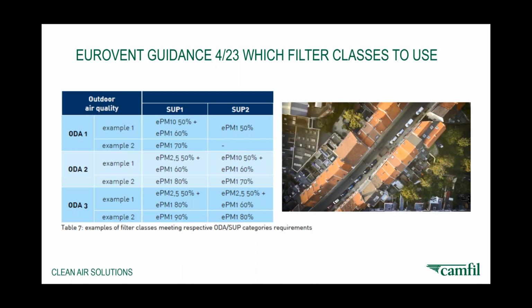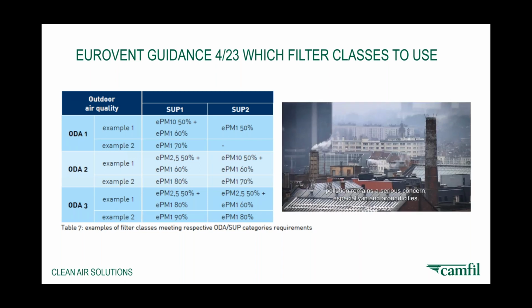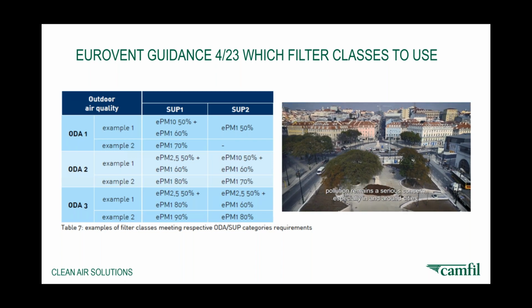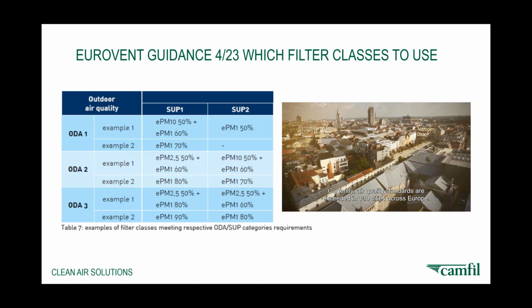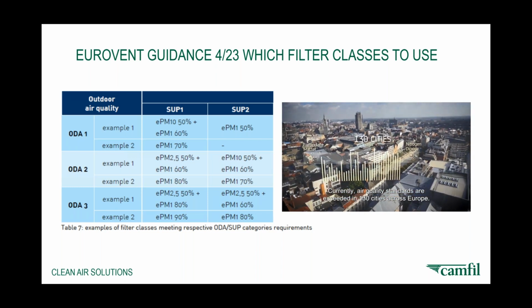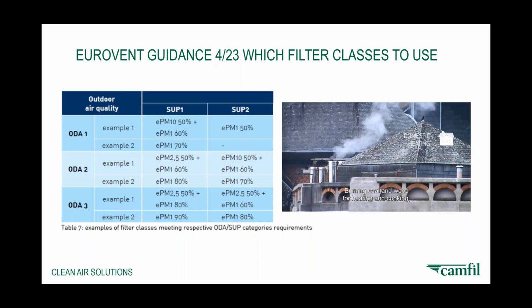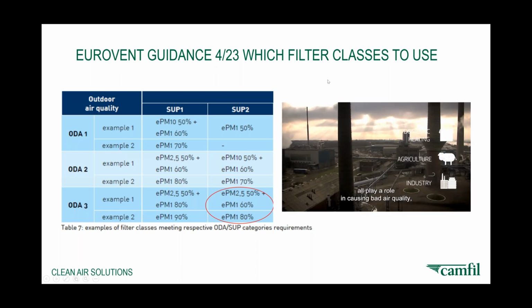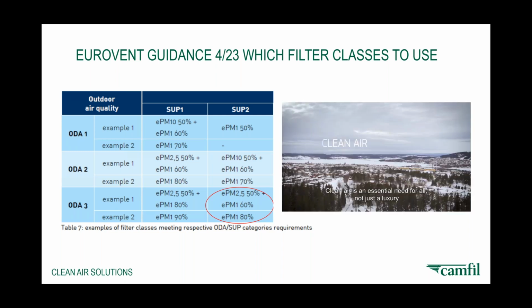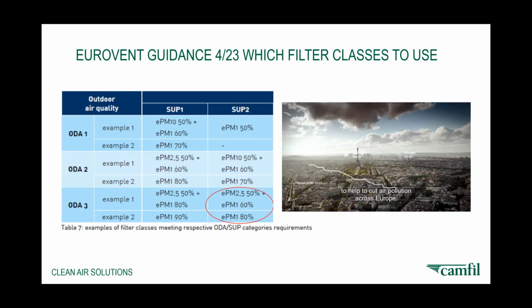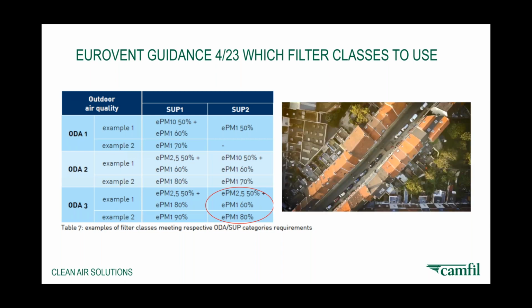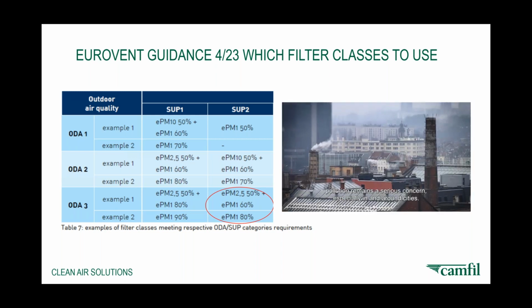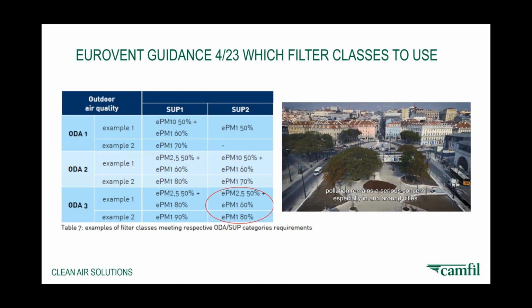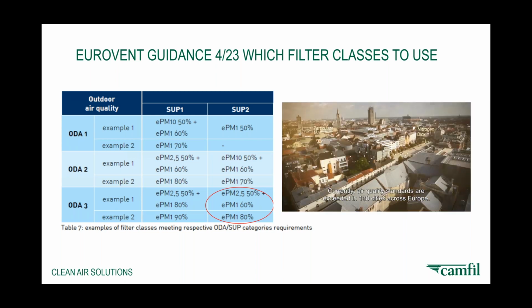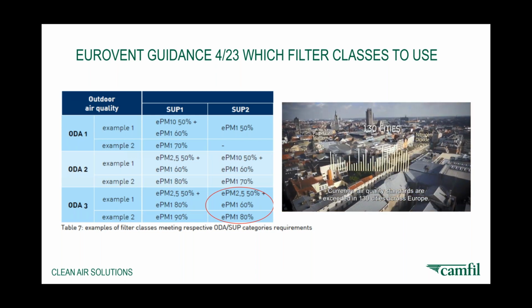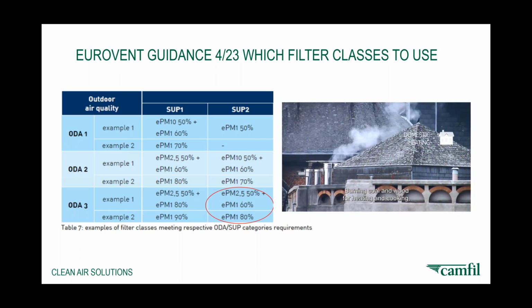And to look at how to achieve, for instance, a SUP2 environment, you would take the area you're in. So let's take an ODA 3 area, a heavily polluted area, and look at the filtration stages that should be used to achieve that class of area. So what they would recommend according to 423 is that you would have either two stages, an EPM 2.5 50% and then an EPM 1 60%, or an EPM 1 80% filter in one stage to achieve a SUP2 class environment in an ODA 3 outdoor environment. So if you want to look at how to achieve various levels of cleanliness in general buildings, I would recommend using the Eurovent guidance.